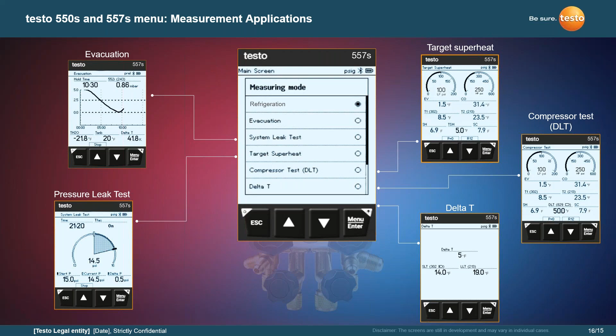For refrigeration measurements with superheat and subcooling, this walks you through everything you need. You'll need either 2 wired pipe clamps or 2 wireless pipe clamps, or even one of each, just so you know the versatility you have in these applications.